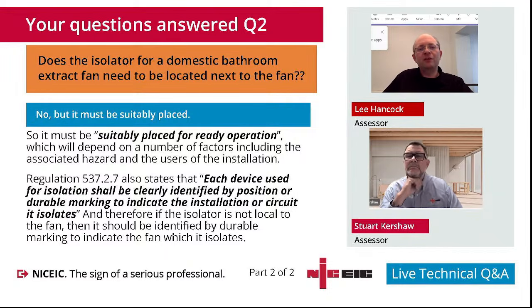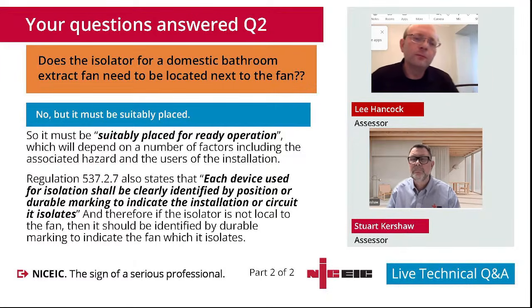Yeah. We shouldn't need to have to climb on something to gain access to it, if that makes sense. So if it's underneath the ceiling on the landing, maybe that's deemed inappropriate these days. Needs to be at a sensible height. Yeah, no, it's good, and real key points that you brought out there, Lee, and especially the one that if it isn't going to be local and is remote, then we need to make sure that we identify what that isolator is for, because it won't be 100% obvious.